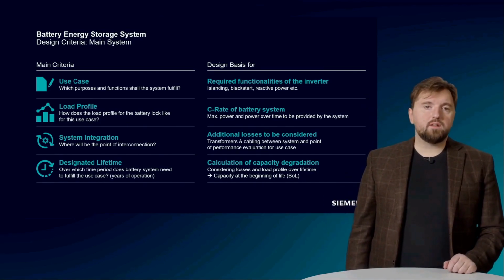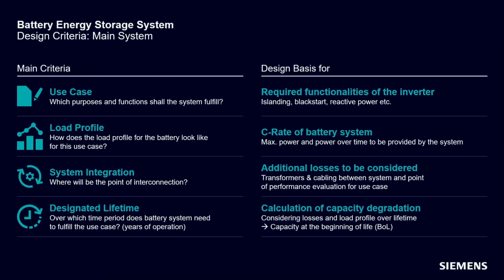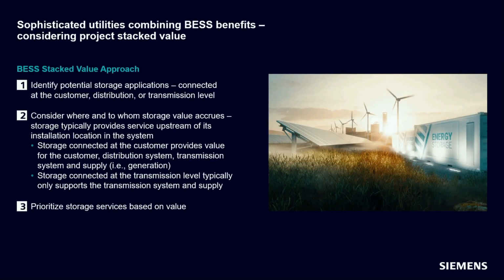Finally, we consider the designed lifetime of the BESS, which tells us how long the BESS should operate effectively. Here, we look at the capacity degradation over time, considering effects of load profile and losses to the BESS lifetime. The idea is to ensure that we start with selecting the adequate initial BESS capacity. BESS can maximize their value to the grid and project developers by providing multiple system services. As some services are rarely called for, for instance black start, or used infrequently in a given hour, such as spinning reserves, designing a BESS to provide multiple services enables a higher overall battery utilization. This multi-use approach to BESS is known as value stacking.